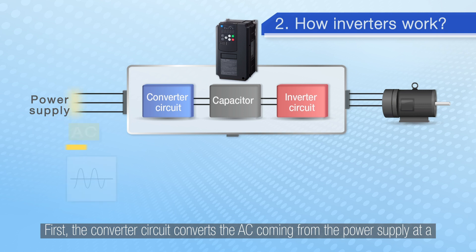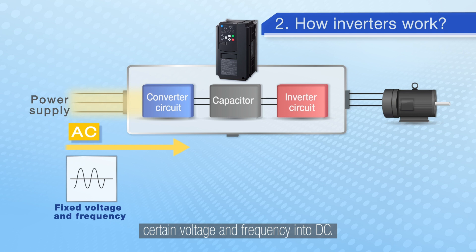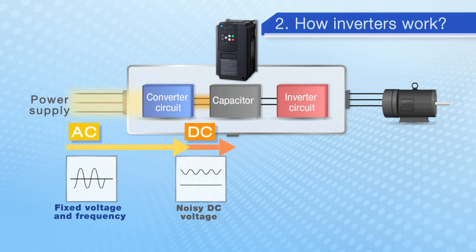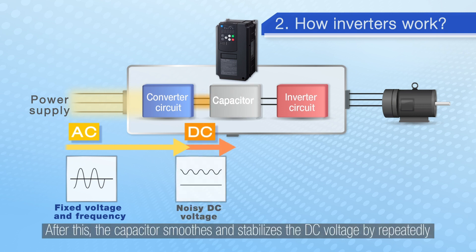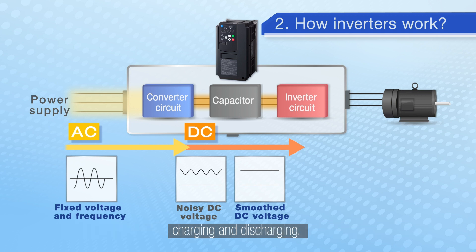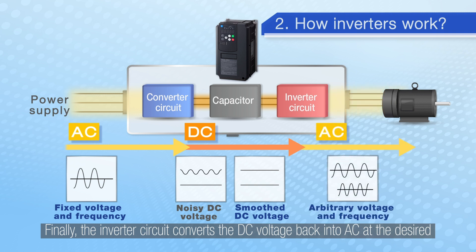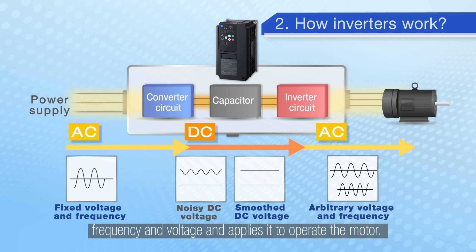First, the converter circuit converts the AC coming from the power supply at a certain voltage and frequency into DC. After this, the capacitor smooths and stabilises the DC voltage by repeatedly charging and discharging. Finally, the inverter circuit converts the DC voltage back into AC at the desired frequency and voltage and applies it to operate the motor.